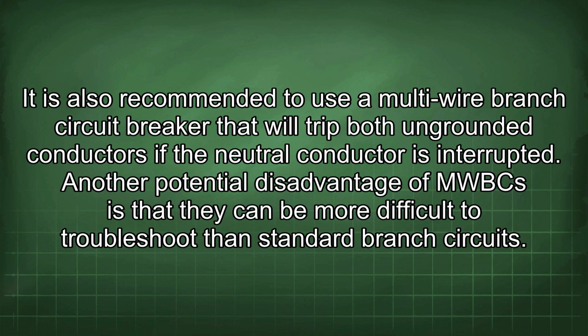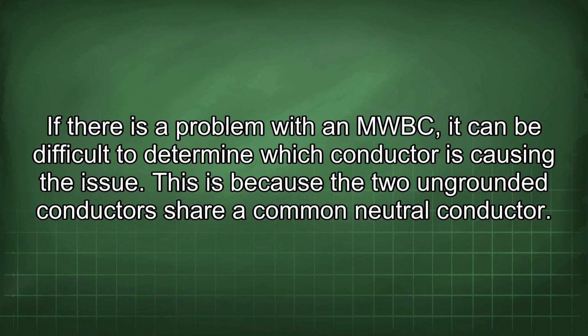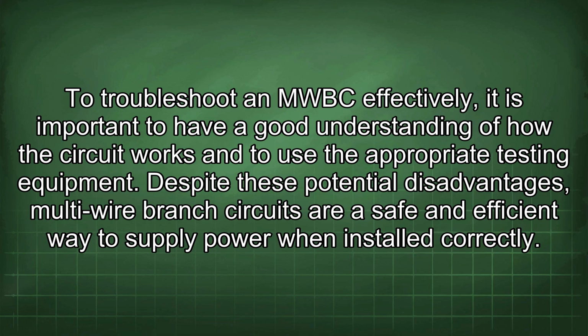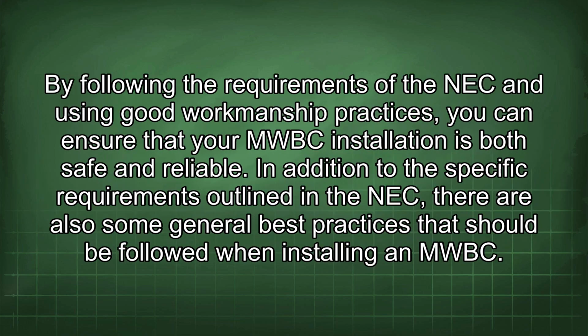Another potential disadvantage of MWBCs is that they can be more difficult to troubleshoot than standard branch circuits. If there is a problem with an MWBC, it can be difficult to determine which conductor is causing the issue. This is because the two ungrounded conductors share a common neutral conductor. To troubleshoot an MWBC effectively, it is important to have a good understanding of how the circuit works and to use the appropriate testing equipment. Despite these potential disadvantages, multi-wire branch circuits are a safe and efficient way to supply power when installed correctly. By following the requirements of the NEC and using good workmanship practices, you can ensure that your MWBC installation is both safe and reliable.